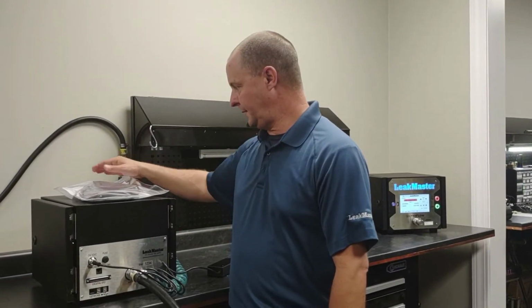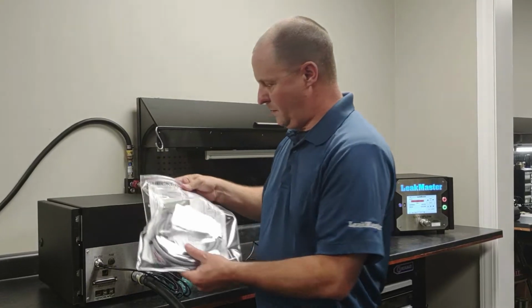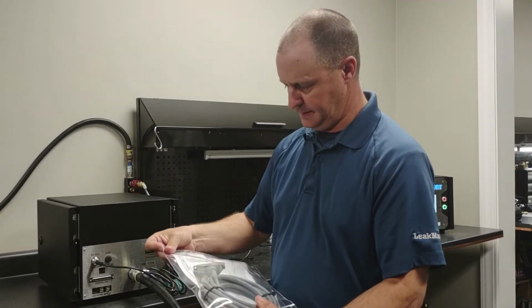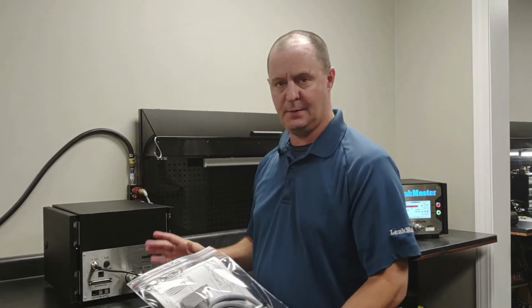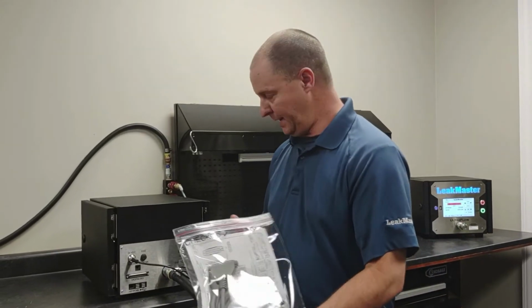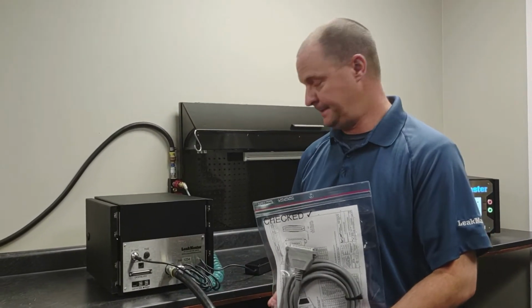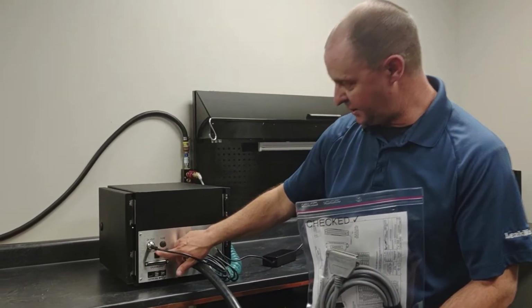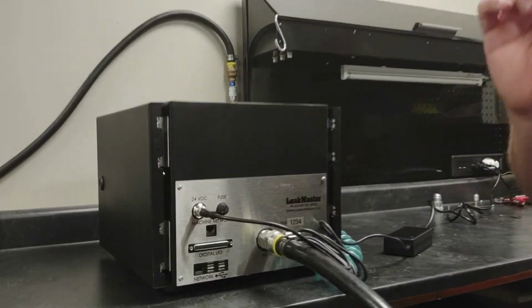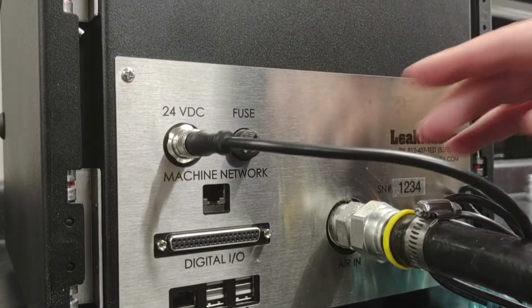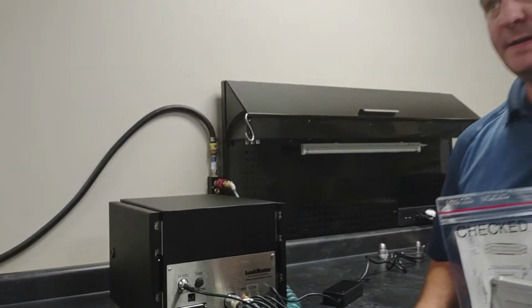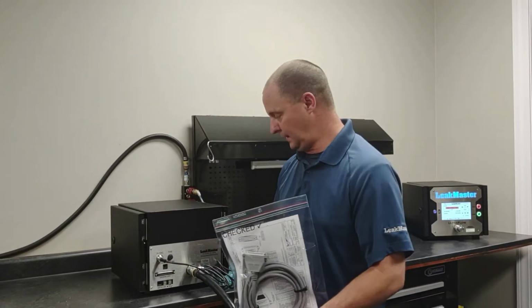Now that you've got power and air plumbed up to the part, for integration purposes, there's going to be a couple ways to communicate with this, and one of them is going to be Ethernet IP, and this is the port right here for machine network. So if you ordered the Ethernet IP or Profinet option, this is the port that you're going to plug into that connects to your PLC network.